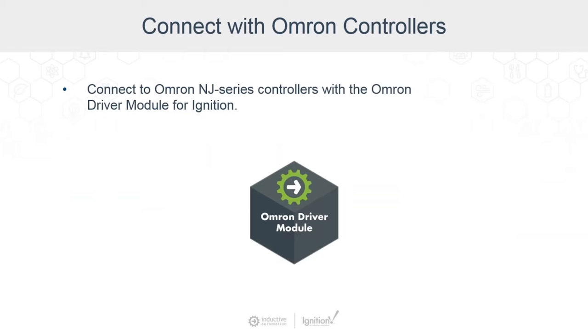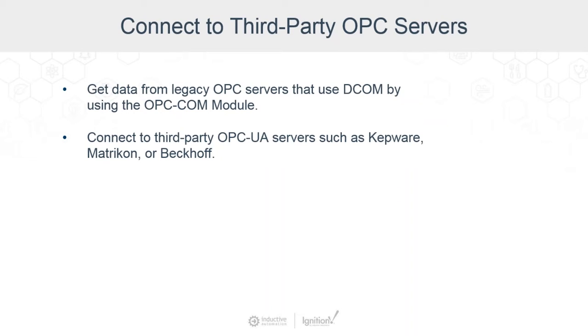Ignition doesn't have drivers for every device — we're not a driver company. We provide drivers for many major industries, but Ignition can connect to various third-party OPC servers, either through DCOM or through OPC UA. Before OPC UA, the original version of OPC used Microsoft DCOM as a uniform way for industrial applications to share data. But DCOM wasn't very easy to work with and has become somewhat outdated. If you have legacy OPC servers that use DCOM, you can get to that data by using the OPC COM module. Ignition also connects to third-party OPC UA servers such as those made by Kepware, Matrikon, and Beckhoff. Because of the standards that Ignition is built on, you can connect to any device — either through Ignition's native OPC or a third-party OPC server.